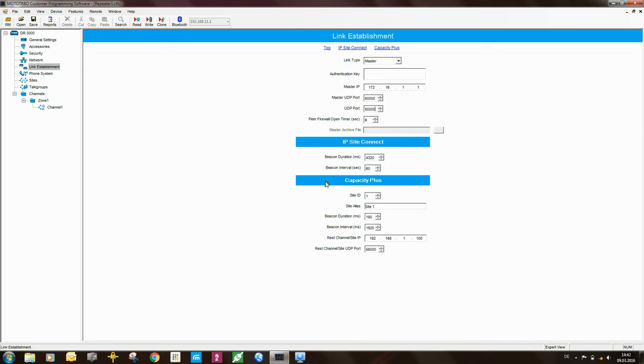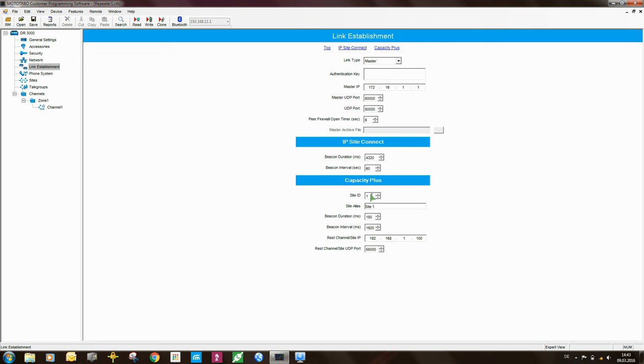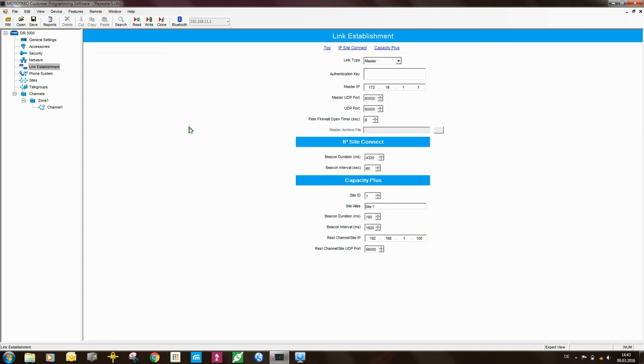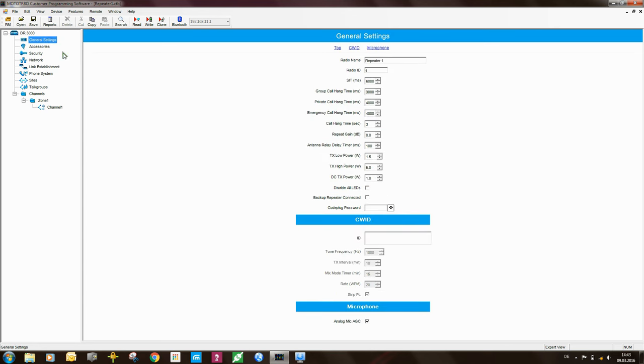The other settings over here you don't need to worry too much about. The settings here for capacity plus you need to be concerned about. The first thing that you need to be sure of is that the site ID is set. So in this case the master repeater is sitting on site 1. So the site ID will be 1. The site alias. Here you would put in a text string to identify what site this is. So in this case I've set this to be site 1. So when you use a tool like RDAC, when you connect you will see the site alias will come up in RDAC as well as the radio name that we set here under general settings.